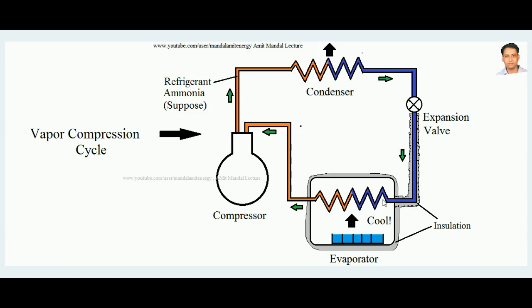In the evaporator, the ammonia absorbs the latent heat of vaporization and again becomes vapor. It enters in liquid form and comes out in vapor form. Since it is absorbing latent heat, the evaporator region cools — this is where the actual cooling action takes place. This vapor ammonia then goes back to the compressor, and the cycle repeats.